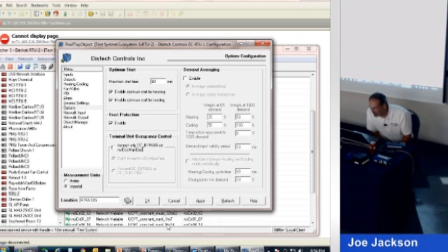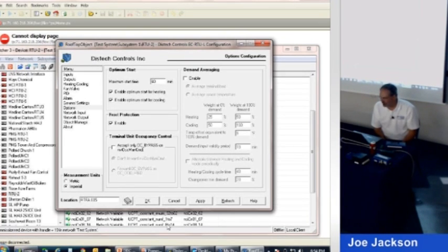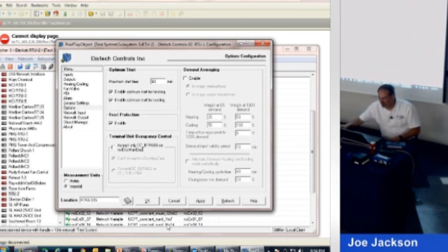This terminal load, because this unit can also be used for a VAV system, it can do some calculations to help you decide whether we're going to bring on the equipment if a VAV box thermostat button gets hit. So because it's LON, it can share data between pieces of equipment. If you tell it that, hey, all these VAV boxes have buttons and I want them to be able to bring the equipment back on, you could check that box, and then any VAV box hitting their button would not only start their VAV box, it would also start the rooftop unit as well.